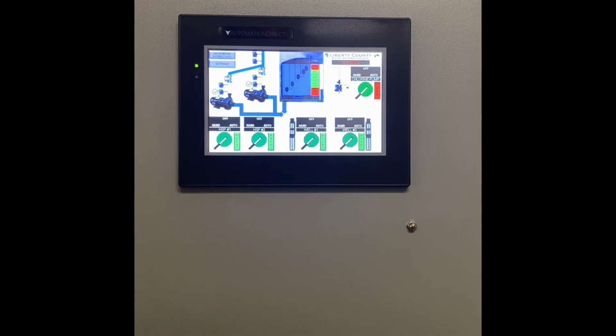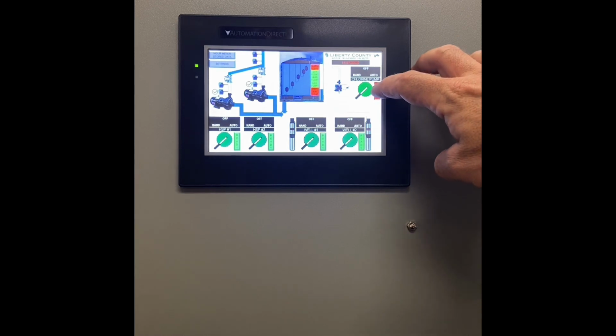If that pump is out of service, the system will ignore it even if it is in automatic because you are working on it. Now, a safety note. It is never good practice to work on a piece of equipment relying solely on a control switch, whether it is a physical switch or a virtual one like seen here. You should always shut off and tag out any source of electricity going to that piece of equipment before you work on it. Now we'll go ahead and put it back in ready.